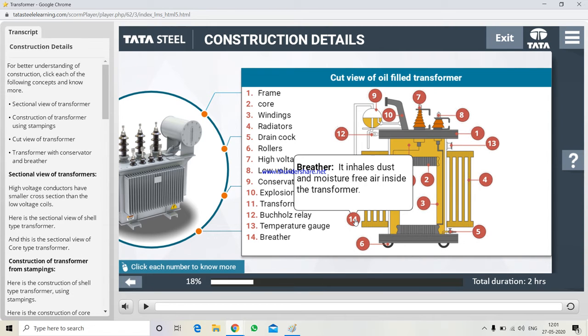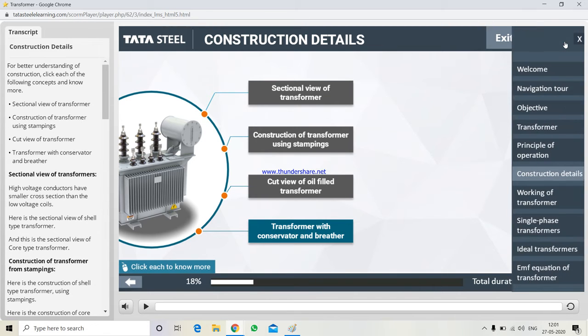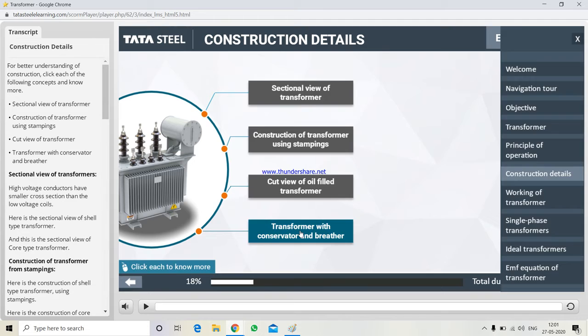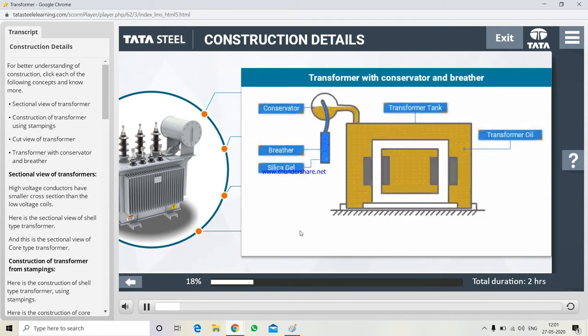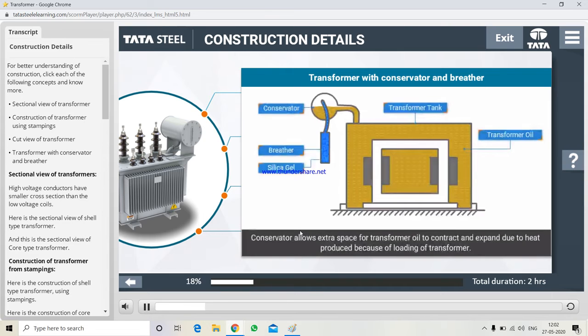Breather. It inhales dust and moisture-free air inside the transformer. Let's understand the working of transformer with conservator and breather. Conservator allows extra space for transformer oil to contract and expand due to heat produced because of loading of transformer. While inhaling, breather allows dry air to go inside the transformer, and during exhaling, the air inside the transformer is released in the atmosphere through it.